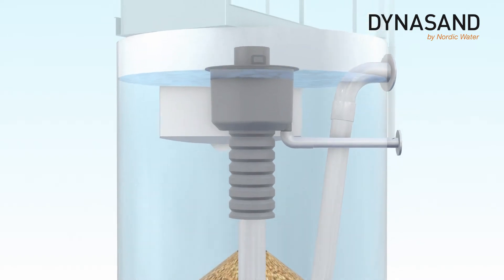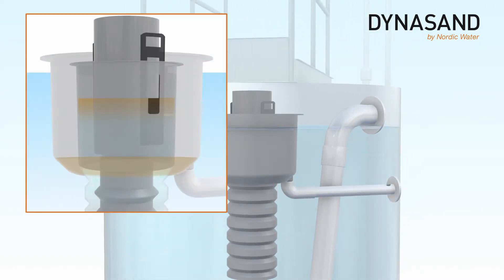The upflow of wash water through the sand washer is generated by a level difference of filtrate and wash water. The level difference is controlled by adjustable weirs, optimizing the sand washing rate and minimizing the wash water used.